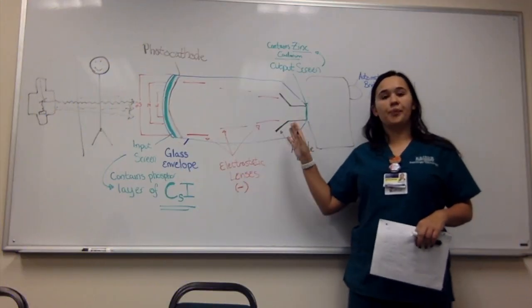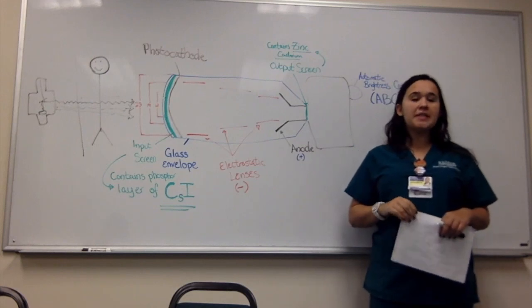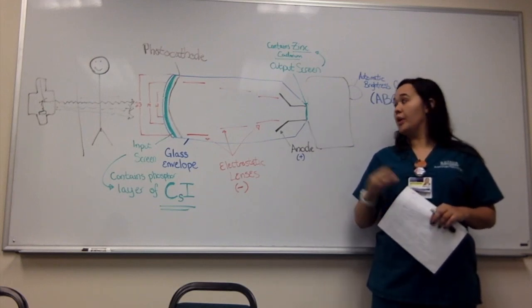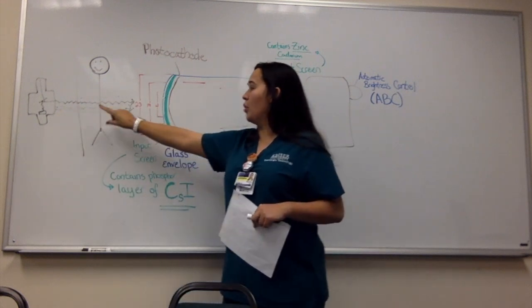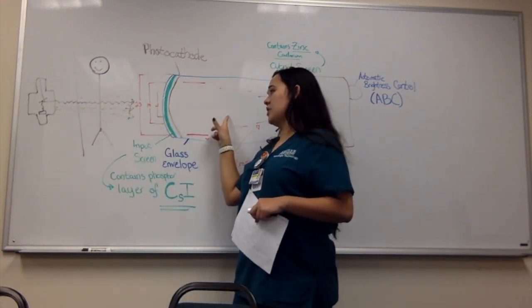This is the image intensifier tube. In fluoroscopy, the image intensifier tube is to increase the brightness. So over here we have the x-ray tube where the photons come out, go through the patient, and towards the image intensifier.